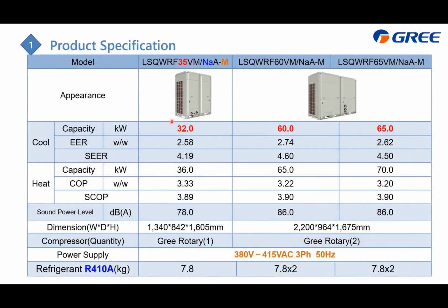And this is the detailed product lineup for the NA, the R410A series. Actually, there are 3 cases of it. It's from 35 to 60, and the maximum is 65. The 35 means the cooling capacity; the nominal is 32 kilowatts. NA means the inside refrigerant is R410A, and the last letter means the power supply, 3 phases.